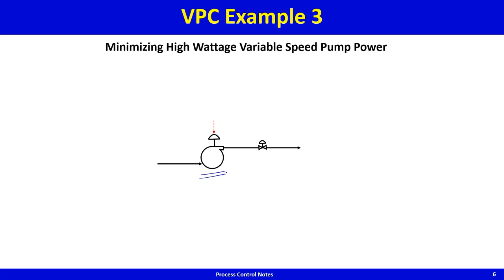The pump speed is set by the operator. The goal is to deliver the demanded flow; a flow controller manipulates the valve to deliver that flow. Now imagine the valve position is only 20% open for a particular flow demand with high variability.